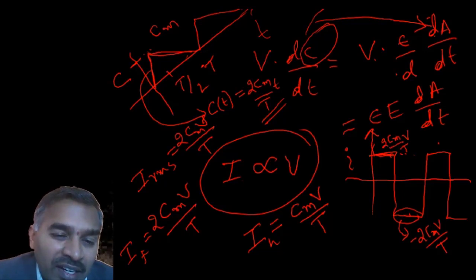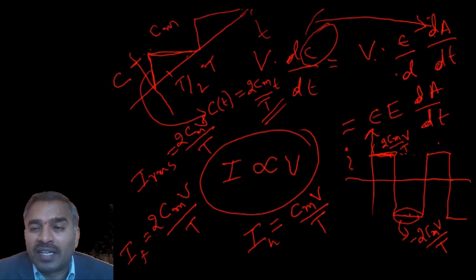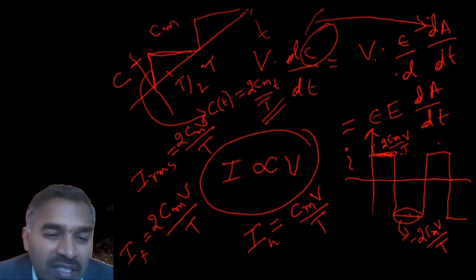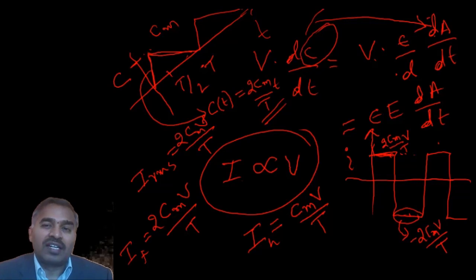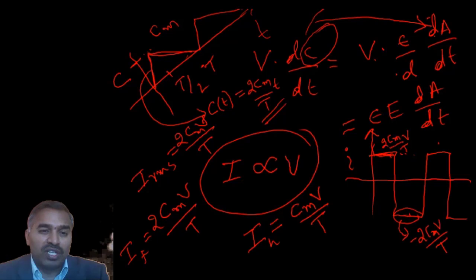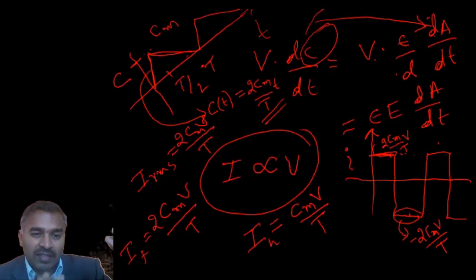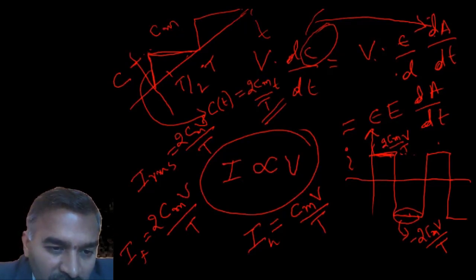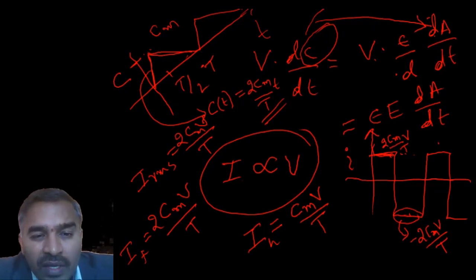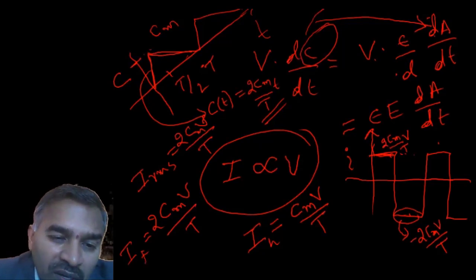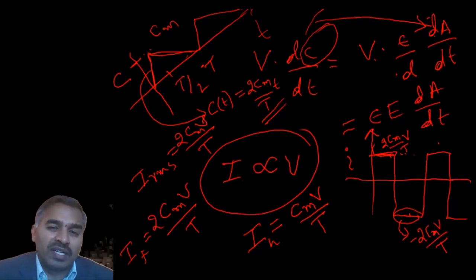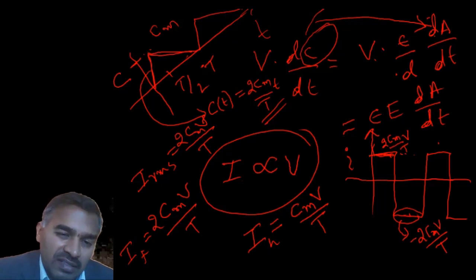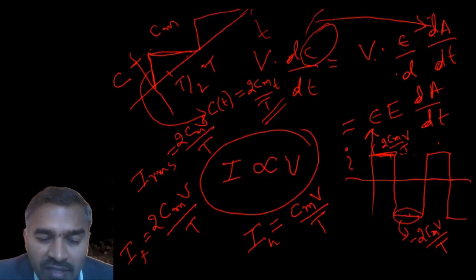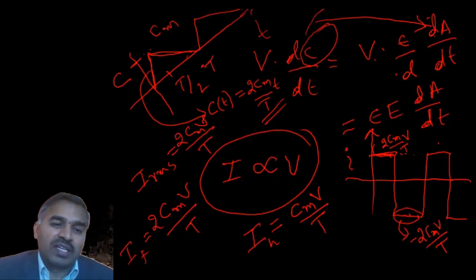And why is that calibration required? Because there is the electric field from a bare conductor with just one insulation, and the electric field with a covered conductor with two insulations. One is the solid insulation on the covered conductor, and the entire air is filled with other gases, air insulation, right? So the calibration worked out for an uncovered or bare conductor is not applicable to a covered conductor, because simply the capacitance value is changing. The capacitance value is now different. So you have to properly calibrate, then it can work.